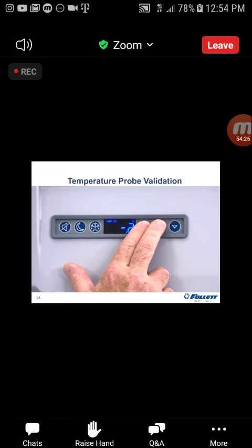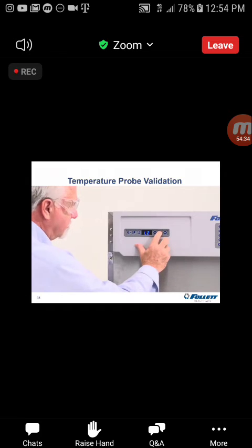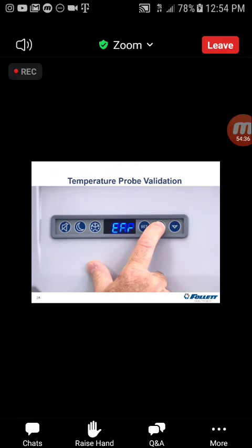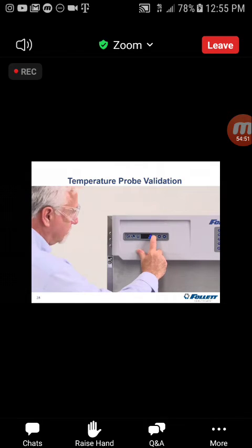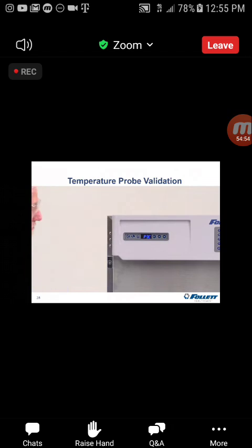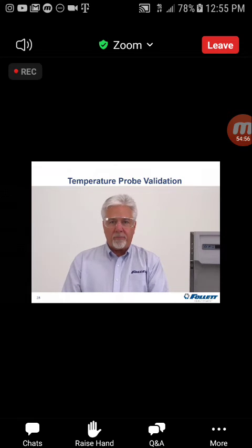The way that you do that is you press the set button and the arrow closest to it, the up arrow, until you see L1 in the display. Then you repeat the process until you see L2. You scroll until you see P3C, which is probe number 3, calibrate. You press set, and the factory setting is 0 degrees. In our example, the probe was reading 0.2 of a degree too low. So we do a plus 0.2 degree offset.